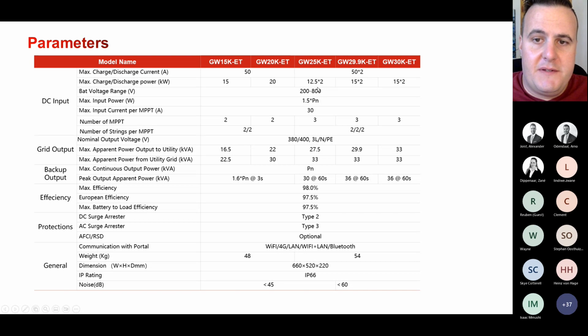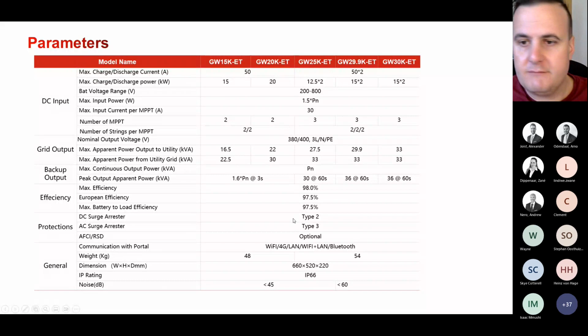We always have to remember with this that we only have 50 amps. If our battery can give us 50 amps, some of the high voltage batteries only give 25 amps on a single tower. Some of them you can put two towers together to make one tower, then you'll have your 50 amps. We just have to make sure we've got enough voltage to actually reach our power target. Especially once we get to the larger inverters, this is going to be more relevant to do that calculation.